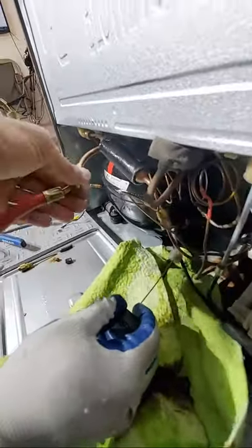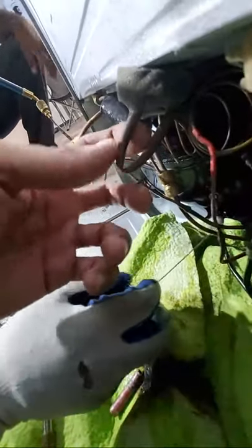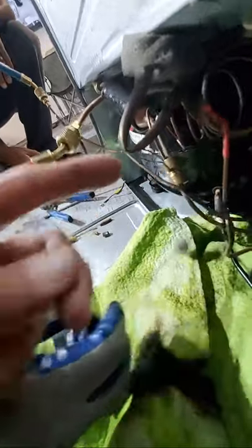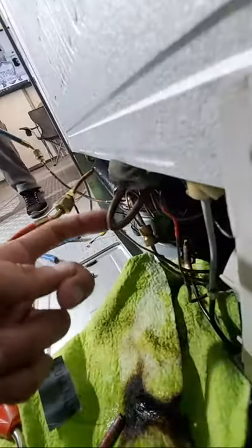And these are tight, right? Cool. I think so. What's this right here? This is horrible. Look at this pinch. Who did this? I did that. This is not good, Peter. You created a little restriction right here. You see that? Yeah. That's not good at all.